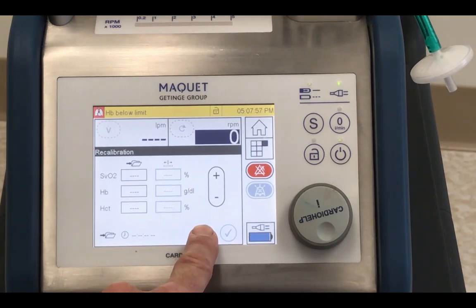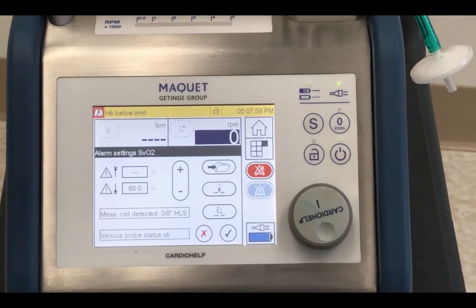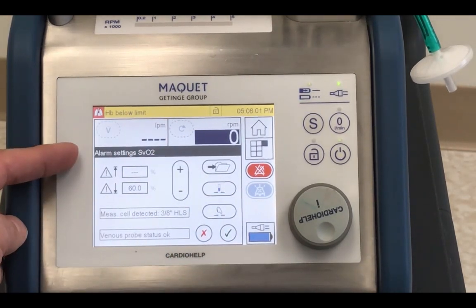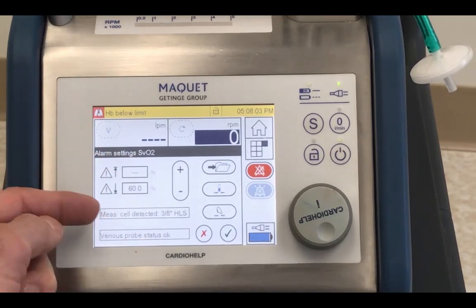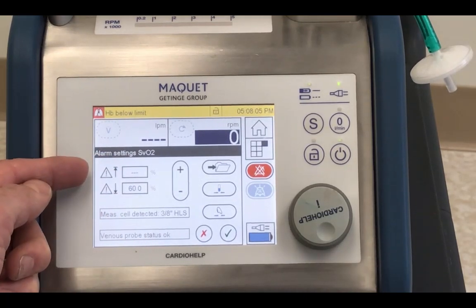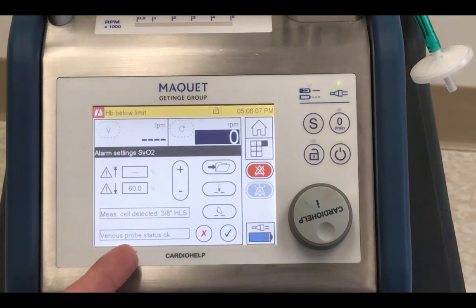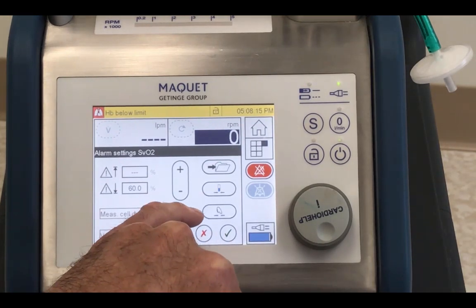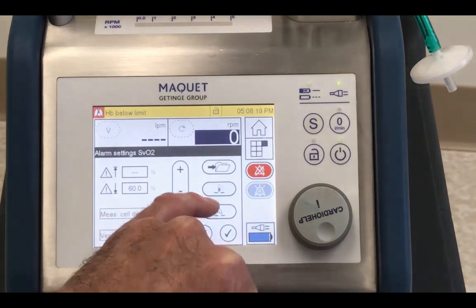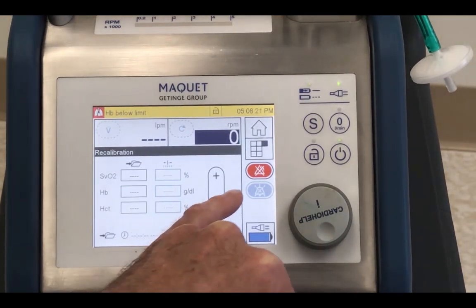I don't have any data, so I have to X out of this. But we've covered the inside of the SVO2 monitor now. This is what it's reading for saturation and hematocrit. It tells you the device that is connected, the status of the probe, and you can recalibrate it during a case. You can save data. You can recall the data. When you recall the data, you can change the data on that screen.